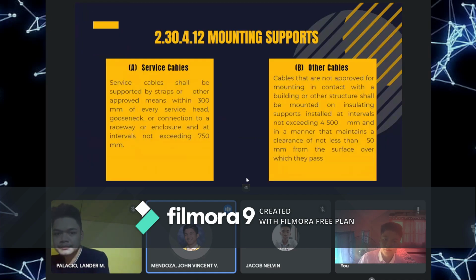So, ang sabi sa mounting supports, next tayo. So, nahati yung mounting support natin para sa service cables and sa other cables. And yung last is yung individual open conductor. So, pangunahan natin sa service cable. Service cable shall be supported by straps or other approved means within 300 millimeter of every service head, goosenecks, or connection to a raceway or enclosure, and at interval not exceeding 750 millimeter.